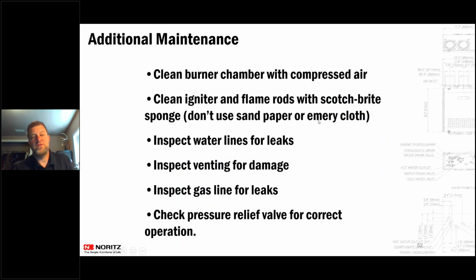So additional maintenance while you're there, you can clean out the burner chamber, clean the igniter. If you are going to clean the igniter on a tankless water heater, on here it says a Scotch-Brite sponge, but don't use sandpaper, emery cloth, or something that aggressive on that flame rod. I've always used a dollar bill to clean those flame rods. A dollar bill is just enough to clean it but not damage it.